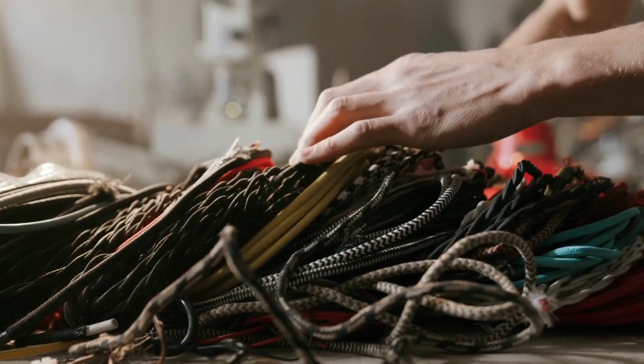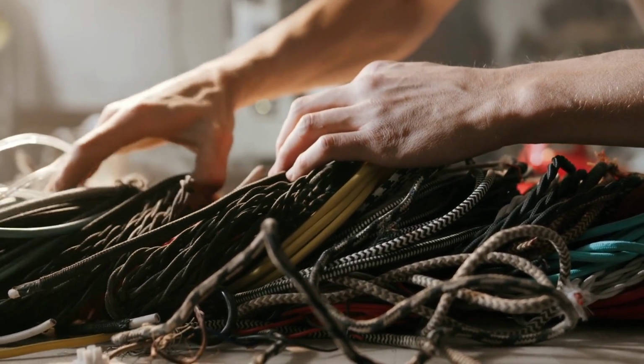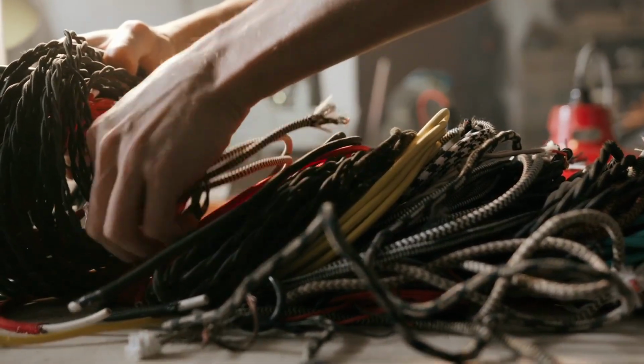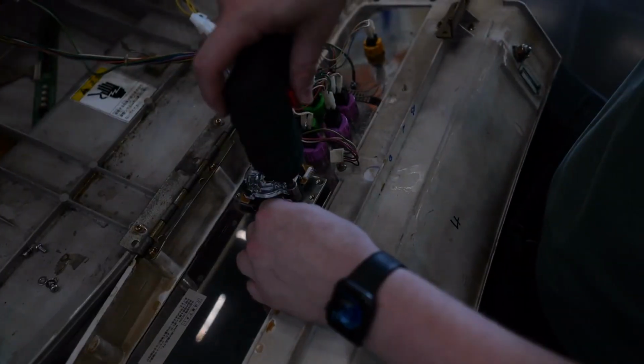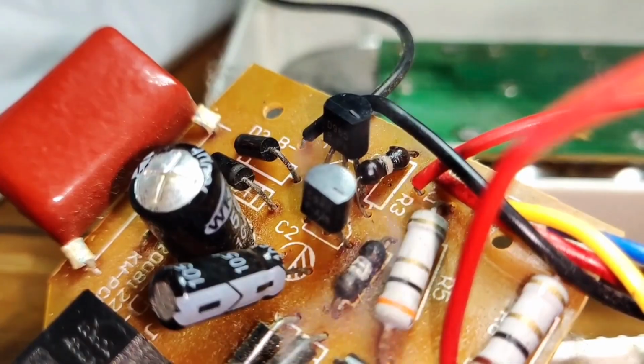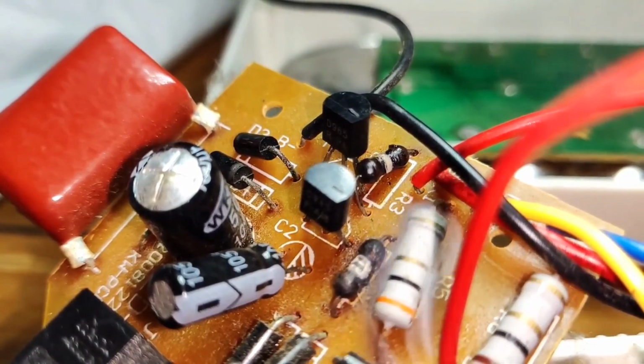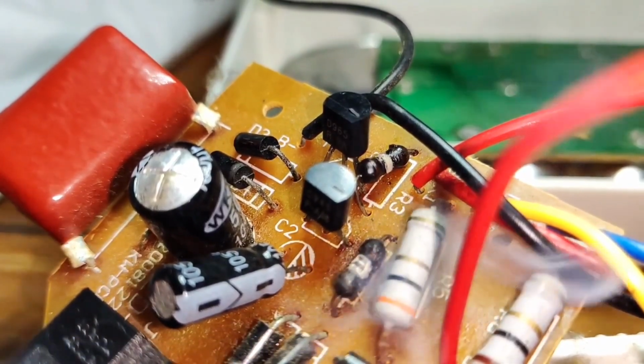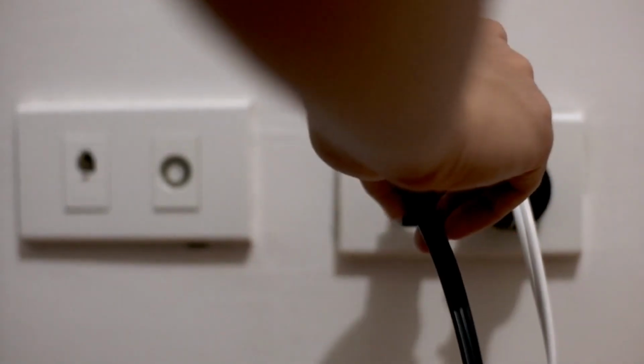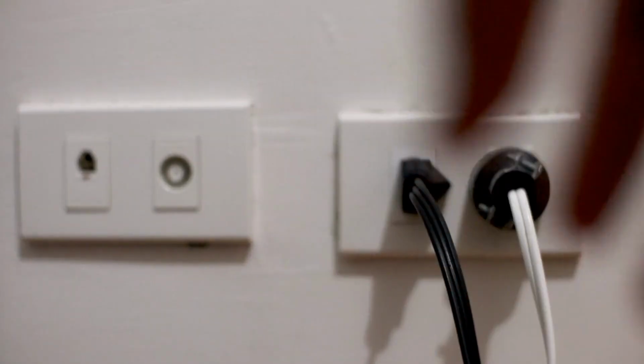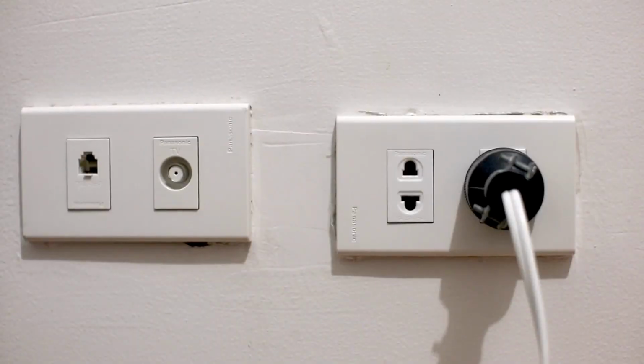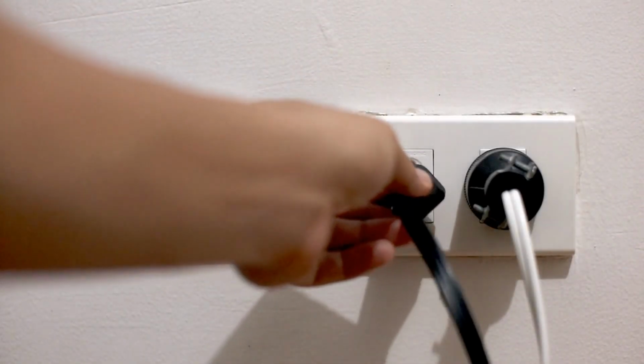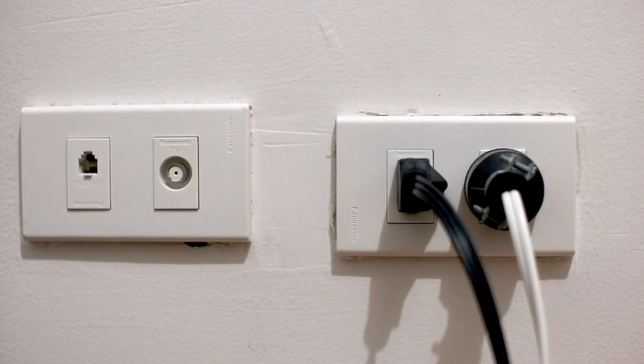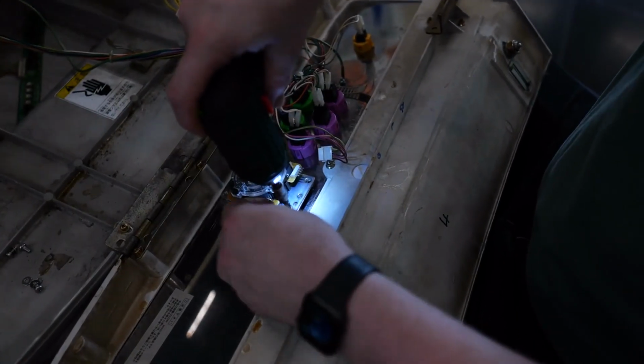Aluminum wiring was used heavily in the late 60s and early 70s because copper prices spiked. The problem with aluminum is that it expands and contracts more than copper when it heats and cools, which means connections loosen over time, which creates arcing, which creates fire risk. A licensed electrician can pigtail aluminum connections with a specific connector and antioxidant compound, but this has to be done at every single outlet and switch in the house. It's doable, but it's labor intensive.